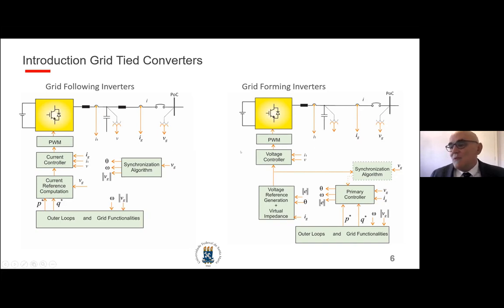In a grid forming converter, you don't have this. Of course, you can have some synchronization to connect the system, but you don't need to have that in there. So what we have is voltage control instead of current control. Again, it's possible to implement with current control, but the most popular method uses voltage control. So the idea is to synthesize the voltage at the POC. And since the converter does not have as large an inductance as we have in a synchronous machine, we have to synthesize this inductance if we want the droop characteristics of a conventional synchronous generator. So often you have to introduce some virtual impedance. It can be resistive, it can be inductive.